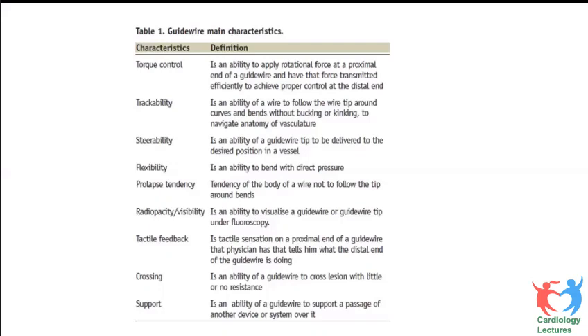Trackability is the ability of the wire to follow the wire tip around curves and bends without buckling or kinking — it needs to take the shape of the vessel. Steerability is the ability of the guidewire tip to be delivered to the desired portion of the vessel, navigating tortuosity, calcified lesions, or acute bends to reach the distal part.